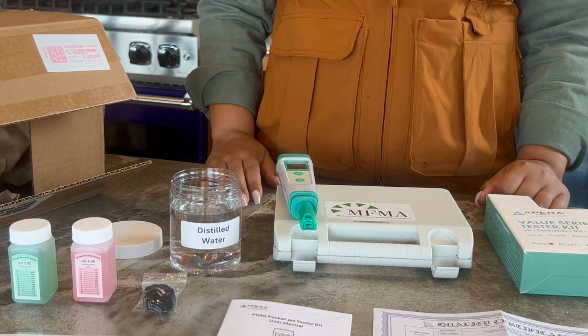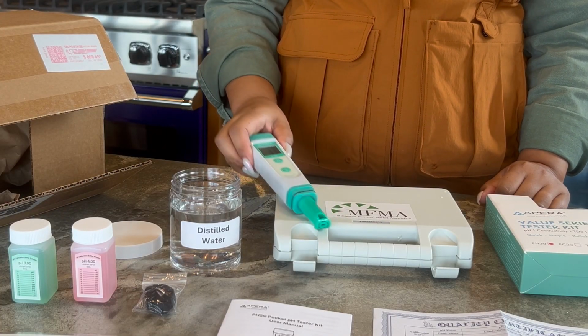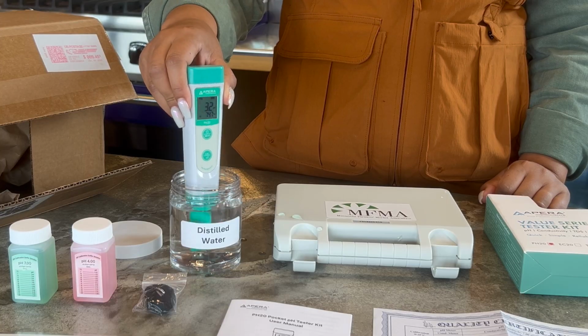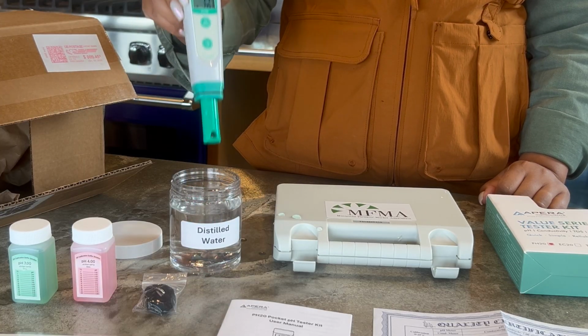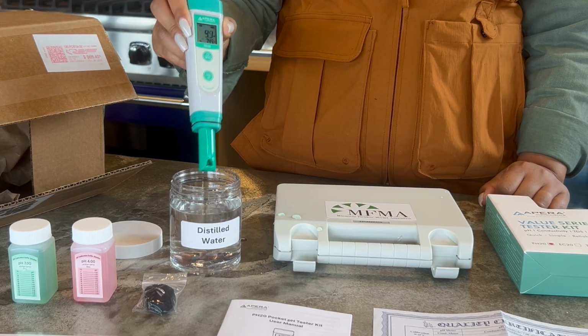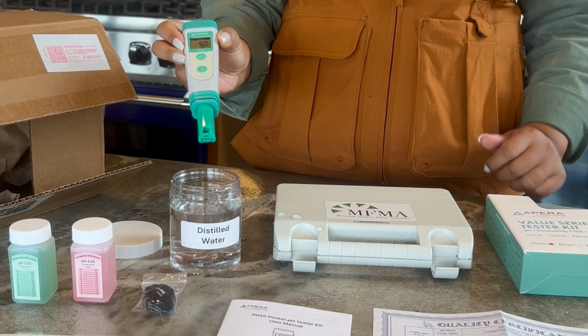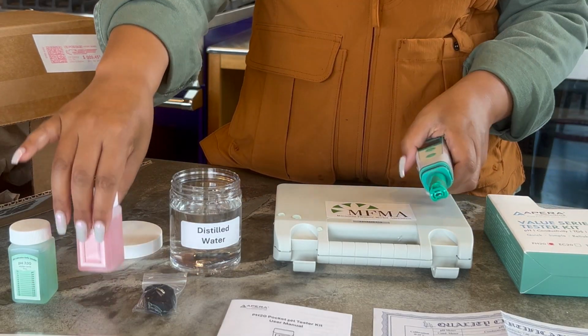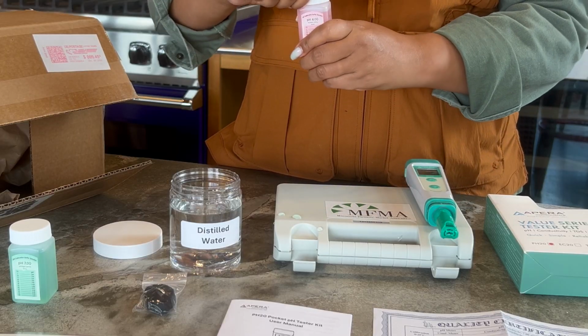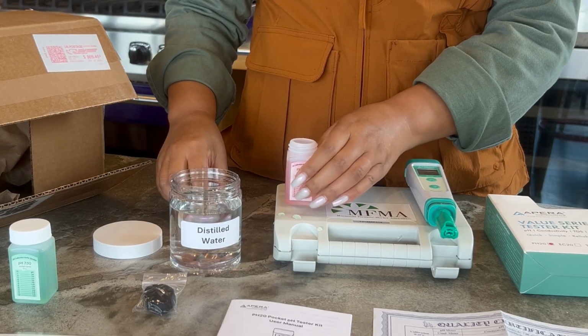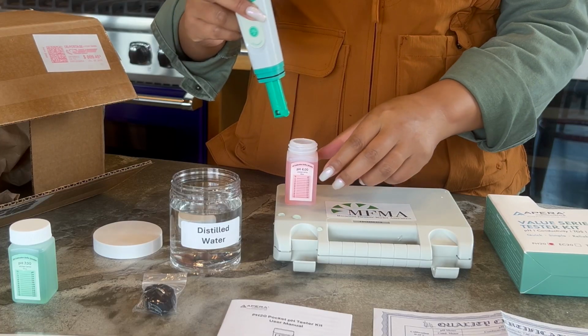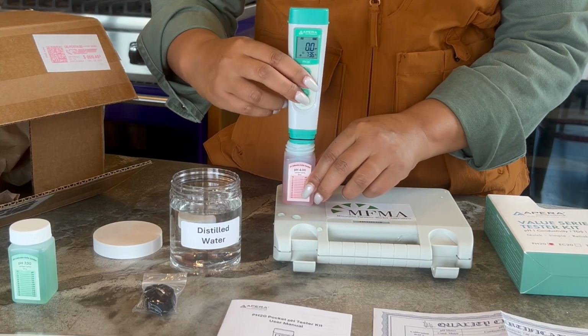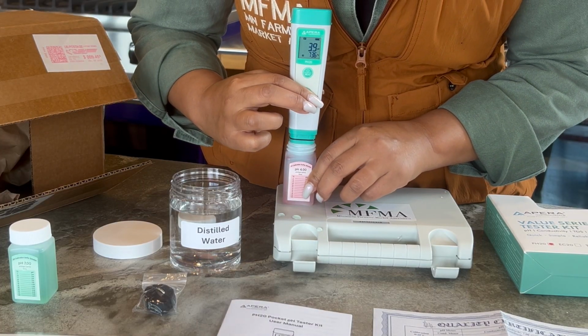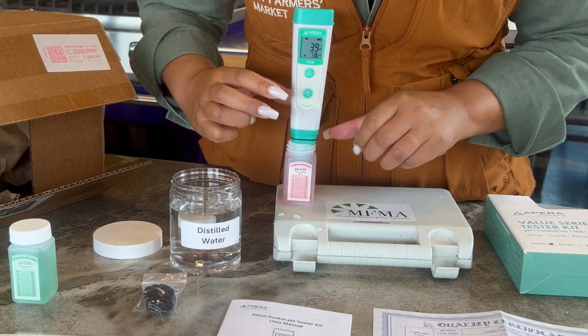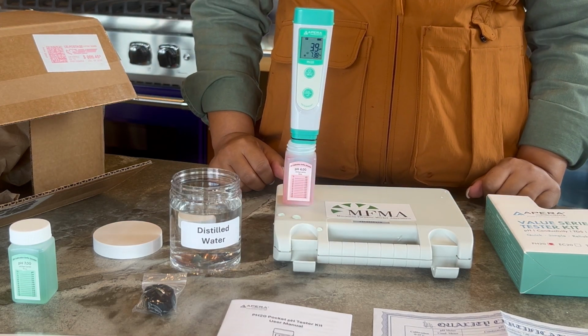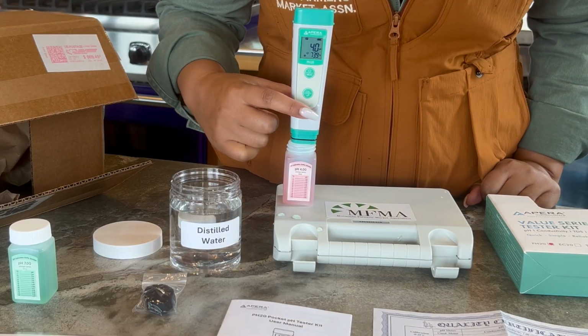Step 4. Swish the probe in the distilled water again to rinse it and shake off excess water. Step 5. Open the jar of 4 pH solution, make a quick stir in the solution, then hold still and long press the cal button to enter calibration mode. Wait for the stable reading when the smiley face appears and stays on the screen. Short press to finish the calibration.